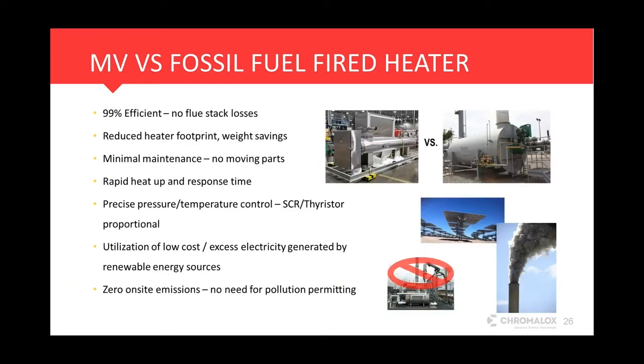So circling back to the electric side, looking at that capability, a medium voltage electric system is nearly 99% efficient. You don't have the flue stack losses. The footprint itself is drastically smaller because you don't have all the ancillary components, like the fire tubes you can see in the picture on the right, that large vessel holding the fire tubes, plus the water and steam portion. That smaller footprint means you can get into places you maybe couldn't fit a gas-fired boiler.